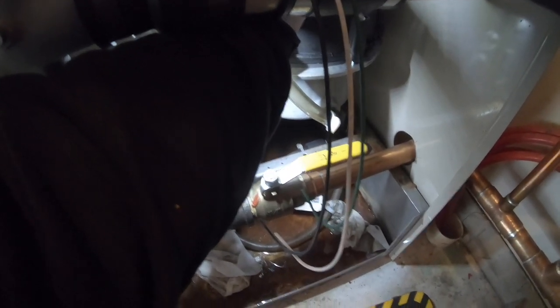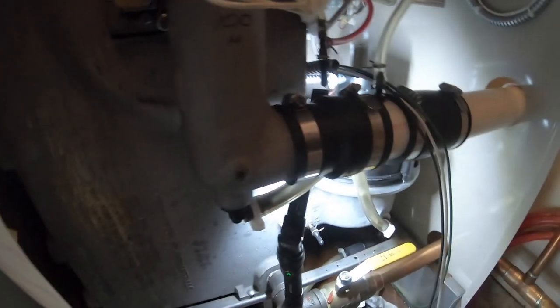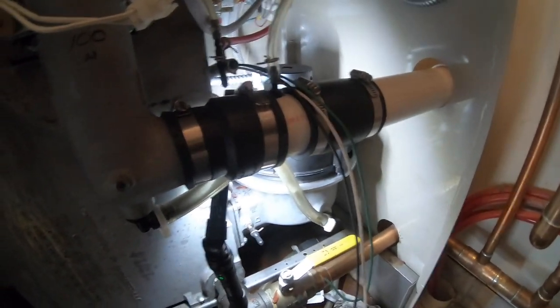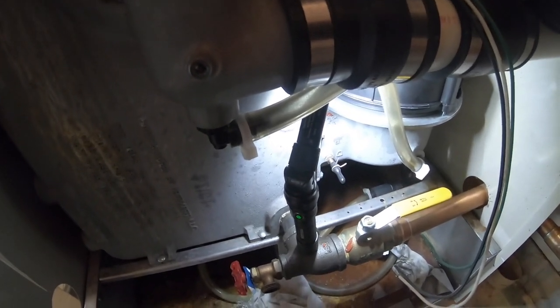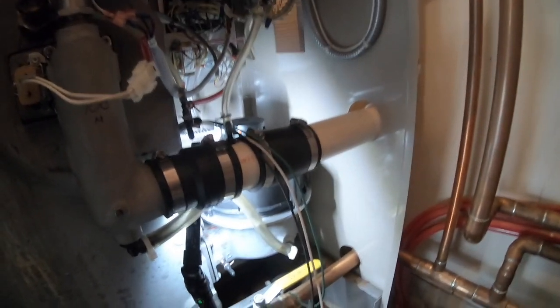Alright, so you know how bad this radiant heat is in the floor. Yeah, this thing's got an internal leak in the floor right now. The heat tubes in the floor. Joe doesn't own this house anymore. It's a different owner. I'm not sure what their last name is. They've had this house for a couple of years now, the new owners. Unfortunately, everything coming off of this that goes for the whole downstairs floor has a leak somewhere in the floor. So we've abandoned it and shut it down.